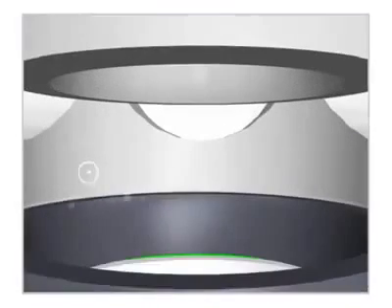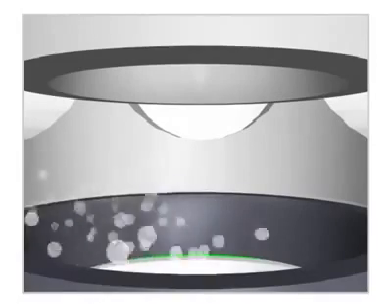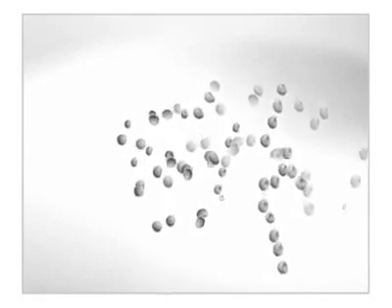Vapor bubbles form in the liquid when the pressure falls to near the level of the liquid's vapor pressure. When the pressure recovers downstream, the vapor bubbles implode and return to liquid form.